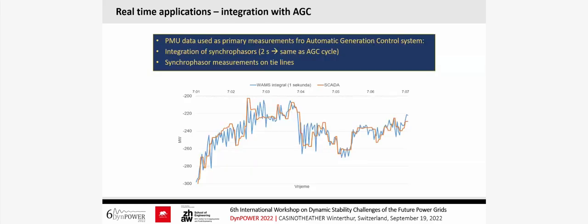Also, we have integrated WAMS system with the AGC system, automatic generation control, because we are installing, and currently in the process of installing, PMUs on our tie lines. This is because we have very large fluctuations of active power on the tie lines in a short time. What we've done is integrate the active power on the tie lines over a 2-second period, which is the AGC period, and send that value to the AGC.